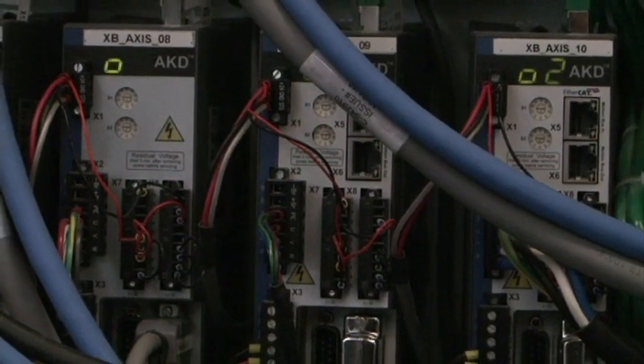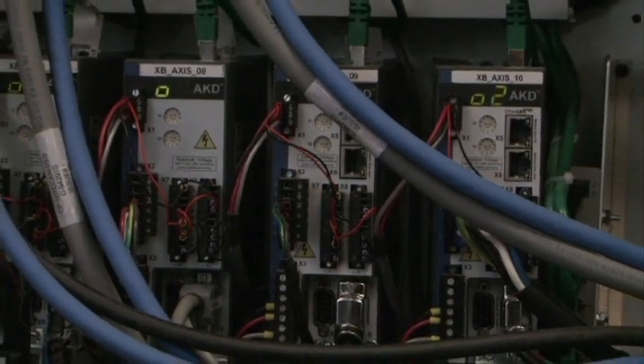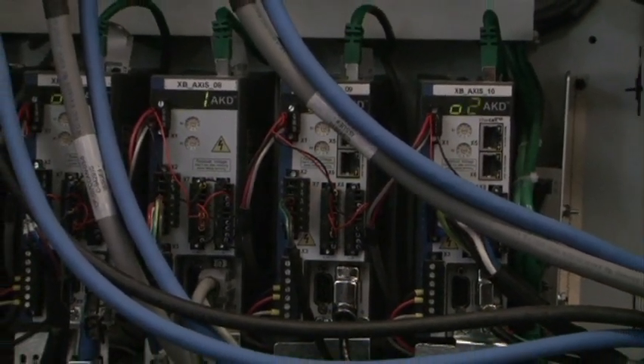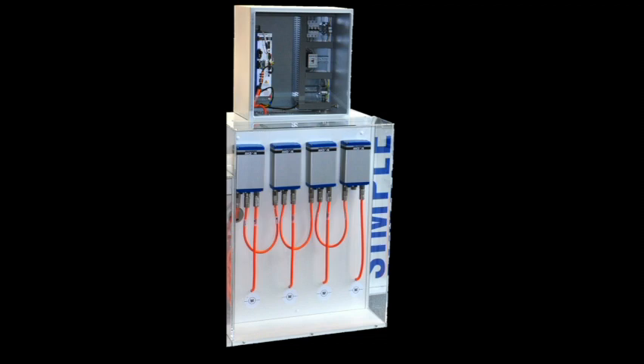Think about a conventional centralized control architecture — since we're talking conventional, this likely means multiple cables: power and feedback for each motor. In a decentralized solution, the motor and feedback cables are condensed into a shorter single cable, and field bus communication and power bus are daisy-chained from the control through a single cable to each local drive.